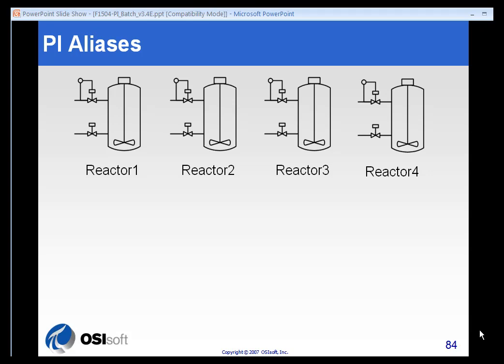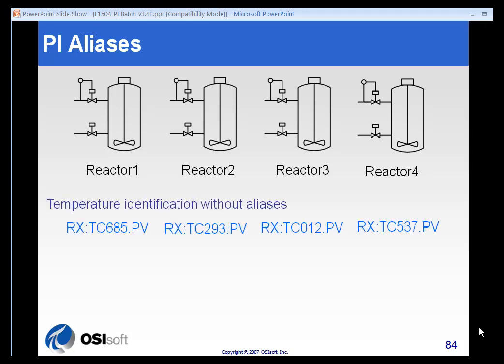Aliasing is a process by which we assign common, more human-readable names to tags that might not otherwise contain indications of what they were monitoring. Here is an example of temperature identification without using aliases. I have four reactors — one, two, three, and four — and these reactors all have temperature sensors in them. Without using aliasing, I would have to know that for Reactor 3, the temperature sending unit was Rx Tc012.pv.